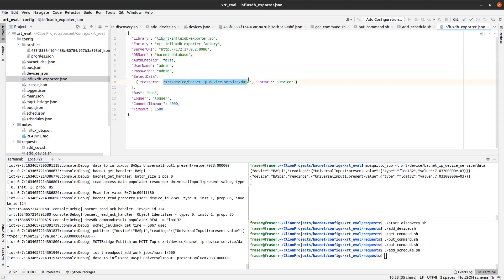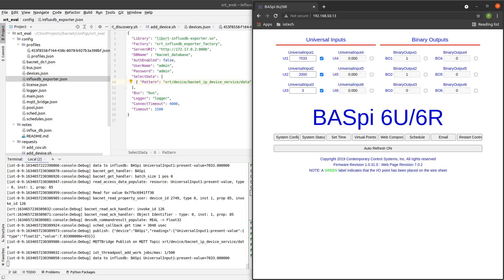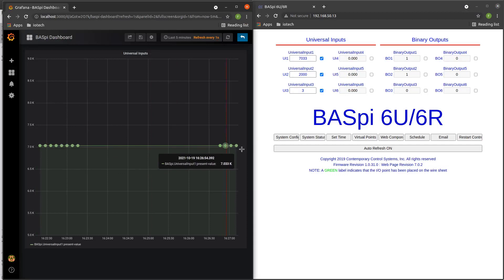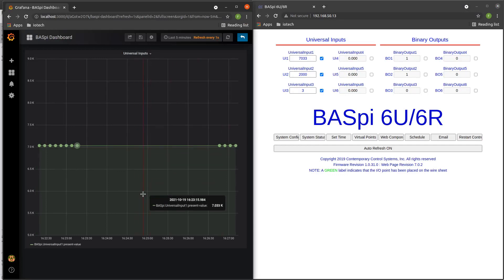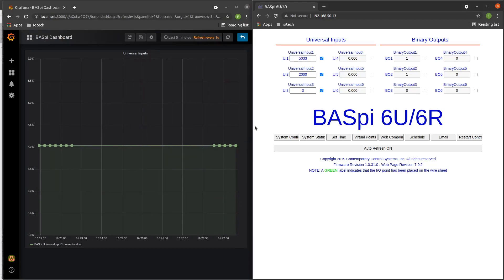As part of this example, we also have an InfluxDB exporter component configured into XRT. You can see the exporter configuration file on the screen. The exporter component is also configured to subscribe to the BACnet data topic and then write each new value to the InfluxDB server, whose IP address you can see in the config file. We have also created a simple Grafana dashboard to display the values of Universal Input 1 which are being read every 8 seconds. If we change the value of Universal Input 1 via the BASPi device console, you can see the data change on the Grafana dashboard.